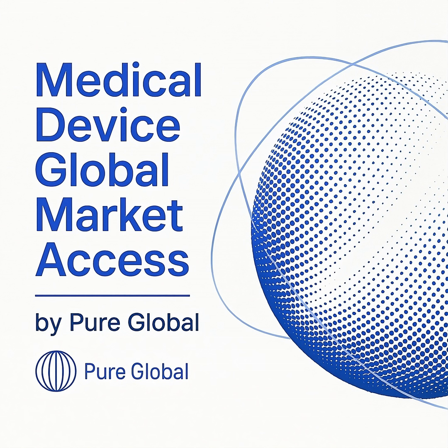Another major deficiency is an incomplete state-of-the-art section. It is not enough to describe the clinical background. You must comprehensively benchmark your device against similar and alternative treatments, using current data to prove your device's benefit-risk profile is acceptable. Equivalence claims are another common stumbling block.